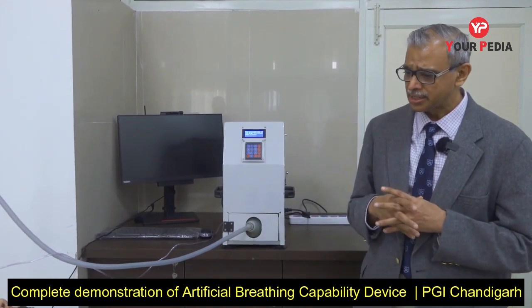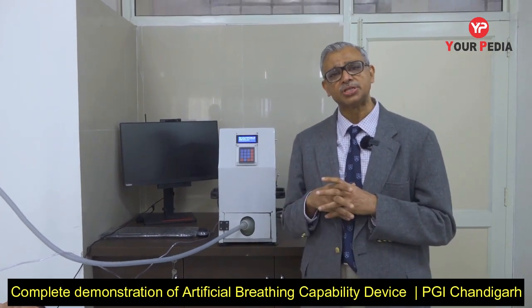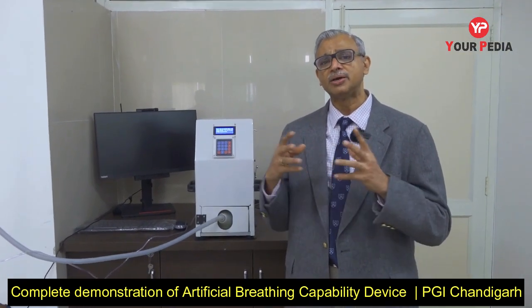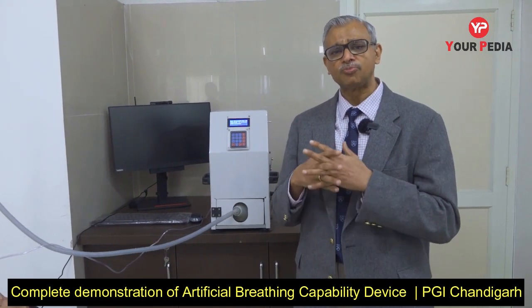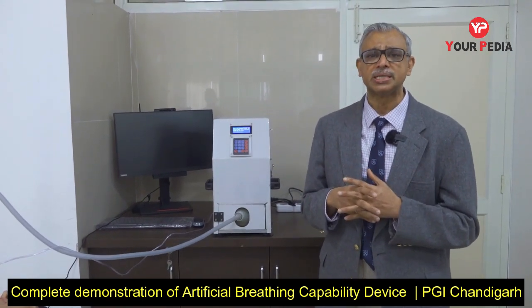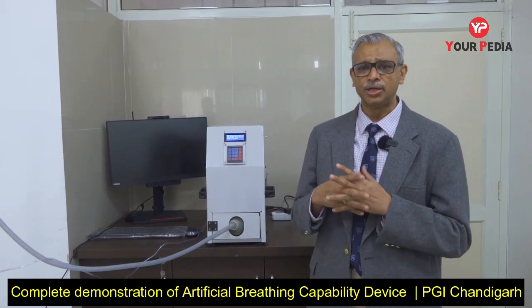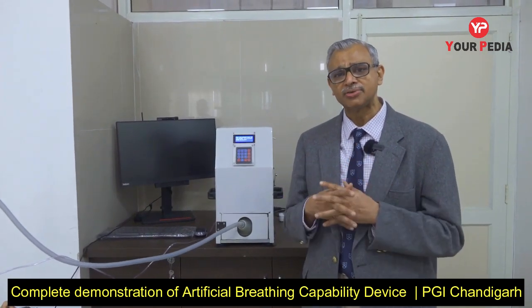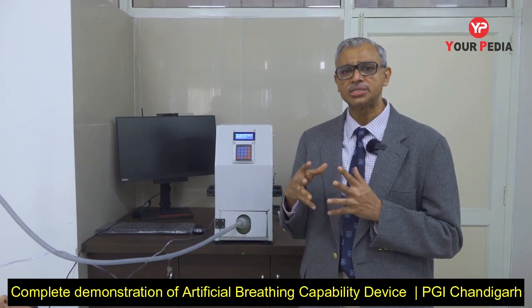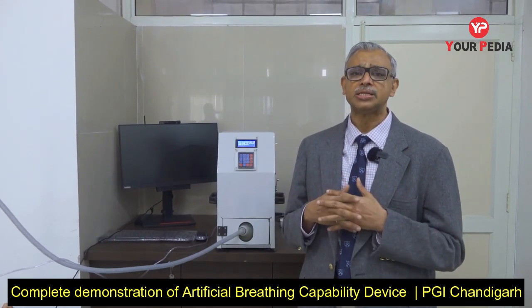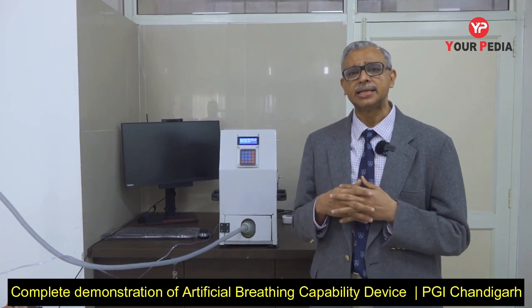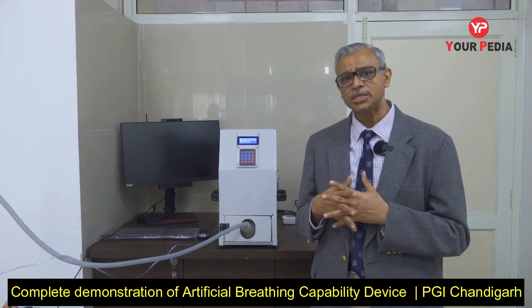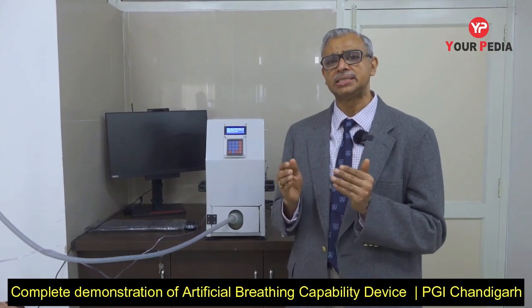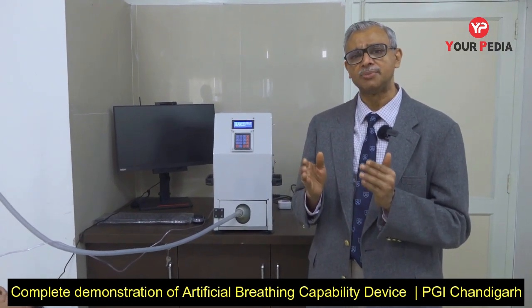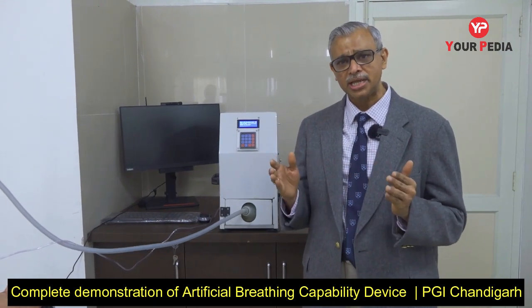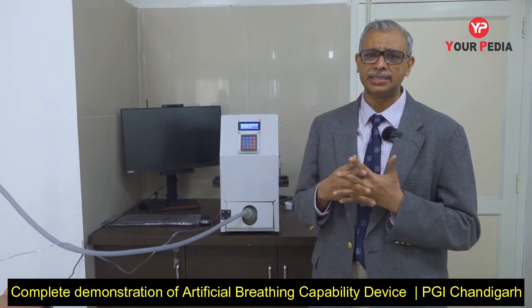I must mention here that some of the copycat devices which came out during the COVID pandemic have been feted in the lay press. A lot of publications have been made in the newspapers and journal articles and also on YouTube. But if you look at where these devices are today, you'll observe that most of these devices are not available to be sold in the market. And the reason is that they don't work. A couple of devices are being sold, but they have limited capabilities in the sense that they have limited application in terms of pressure range, respiratory rate range, and also the volume which can be delivered and the inspiratory to expiratory time ratio.